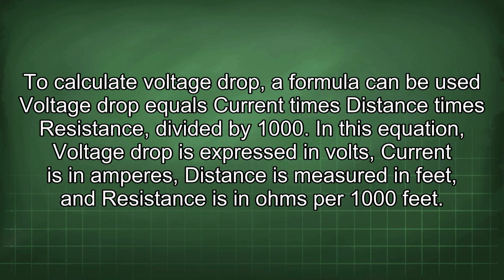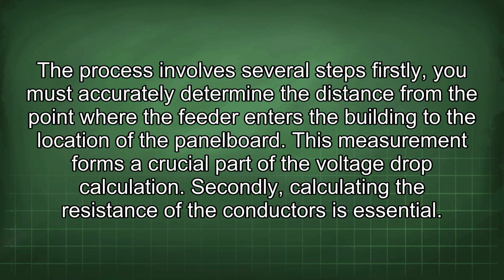To calculate voltage drop, a formula can be used: voltage drop equals current times distance times resistance, divided by 1000. In this equation, voltage drop is expressed in volts, current is in amperes, distance is measured in feet, and resistance is in ohms per 1000 feet. The process involves several steps. Firstly, you must accurately determine the distance from the point where the feeder enters the building to the location of the panel board. This measurement forms a crucial part of the voltage drop calculation.